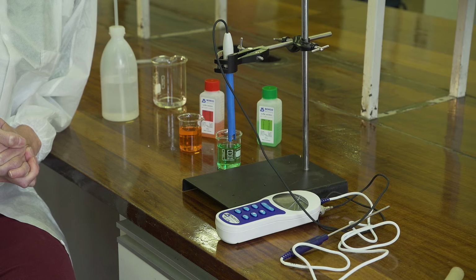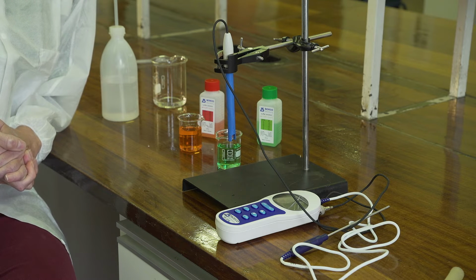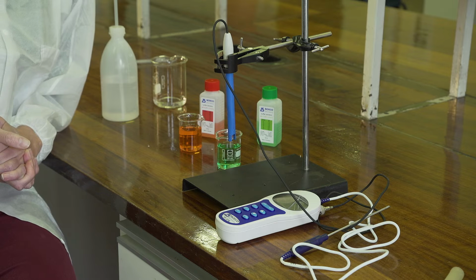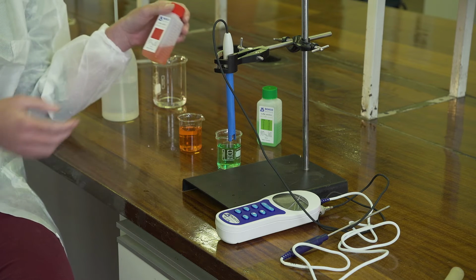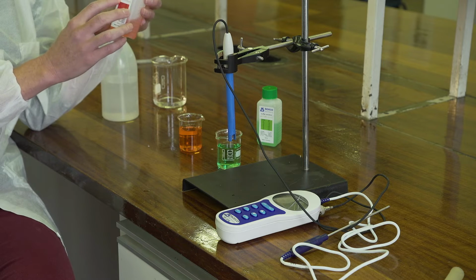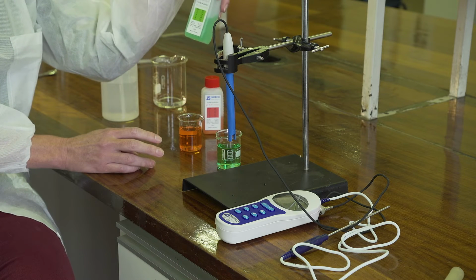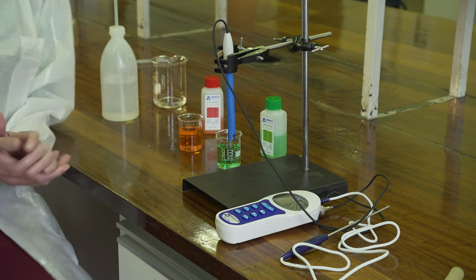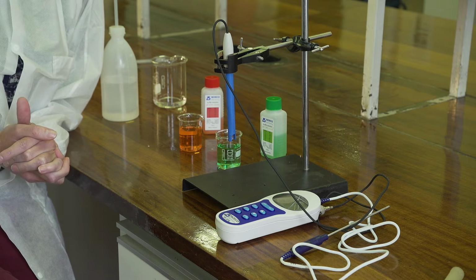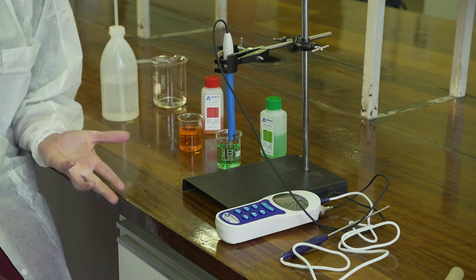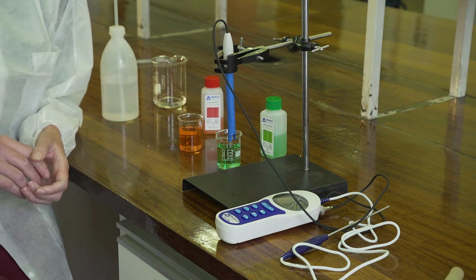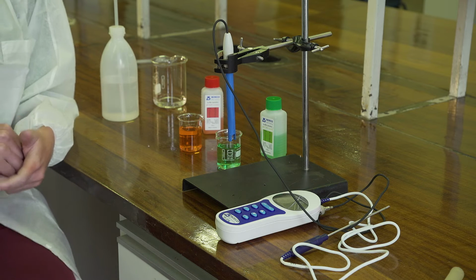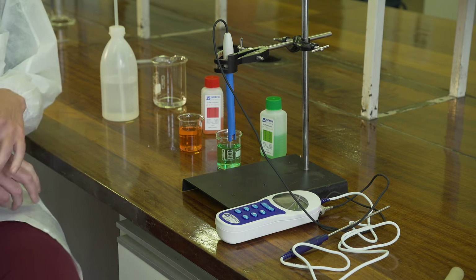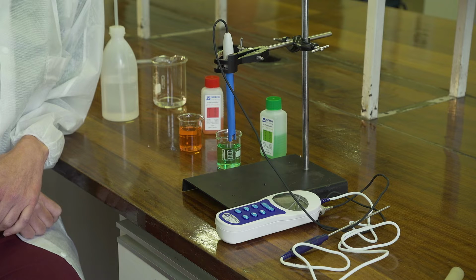The second part of the analysis is to measure the element of interest, which in our case now is a hydronium ion, H+. We are going to be using an automated pH reader to do this. And before we begin with our actual soil analysis, we must calibrate this meter. We're going to be using a pH buffer solution 4.0 and also a pH solution of 7 to calibrate the reader. We're also going to be using a temperature probe to adjust for temperature. We'll be correcting the pH for temperature. It automatically corrects for temperature.